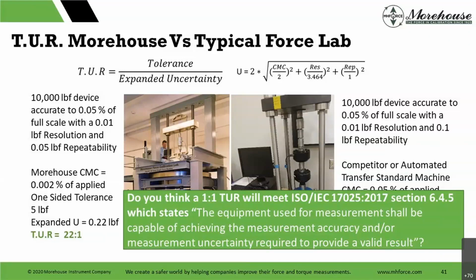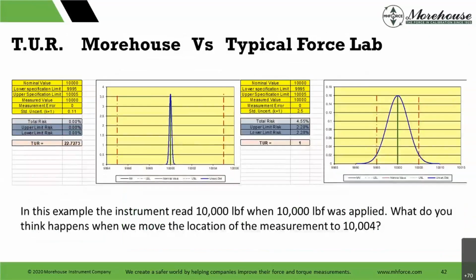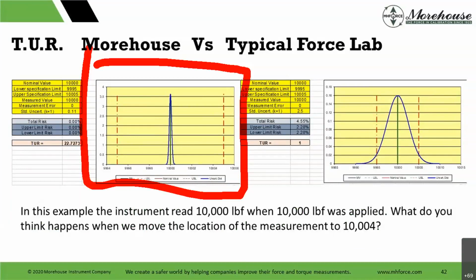So in regards to this, the question is, do you think a one-to-one ratio is good enough to achieve the desired result? Maybe it is, maybe it's not. In this example, the instrument was read to 10,000 pounds of force. Here, the T.U.R. on the left is us, dead weights. Just think about this, dead weights. On the right, an accredited calibration service provider.